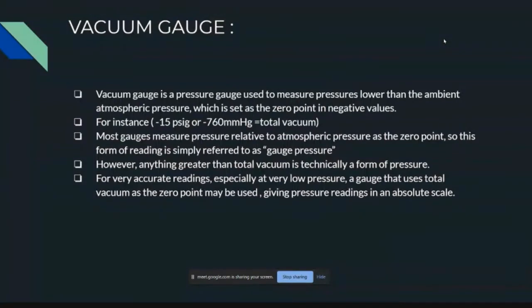A vacuum gauge is a pressure gauge used to measure pressure lower than the ambient atmospheric pressure, which is set as the 0 point in negative values. For instance, minus 15 psig or 760 mm Hg equals total vacuum. Most gauges measure pressure relative to atmospheric pressure as the 0 point, so this form of reading is simply referred to as gauge pressure. However, anything greater than a total vacuum is technically a form of pressure. For accurate reading, especially at very low pressure, a gauge that uses total vacuum as a 0 point may be used, giving readings on an absolute scale.